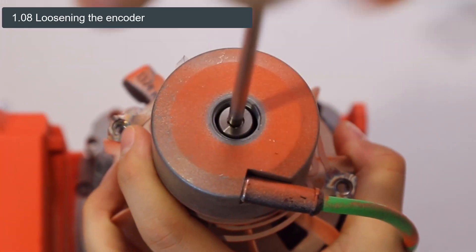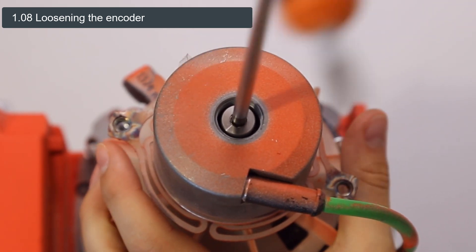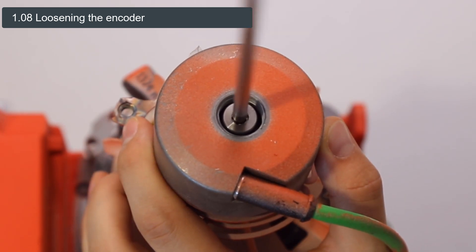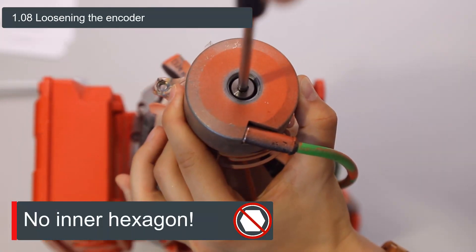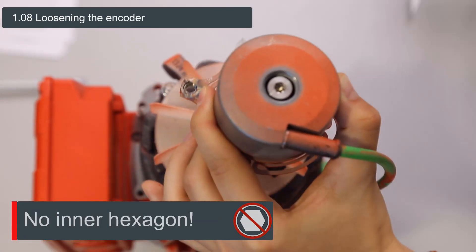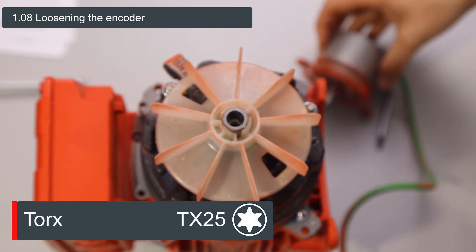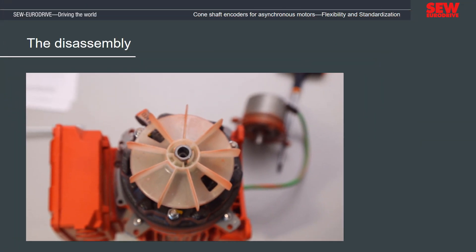It is important to know that after overcoming the torque, the screw can be loosened easier at first but becomes more difficult later on until the encoder can finally be removed. Please do not use the inner hexagon socket, as this would open the encoder. Instead, only use the Torx socket. The disassembly of the cone shaft encoder is now complete.